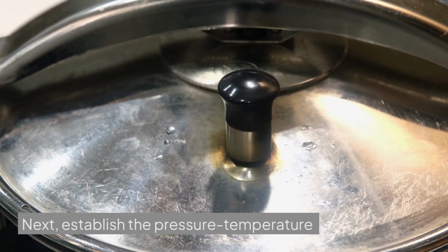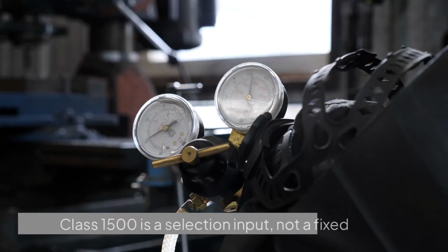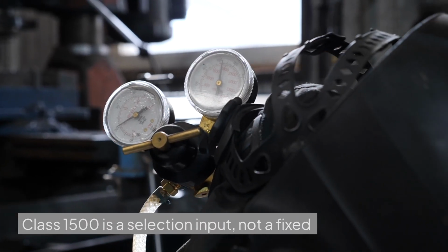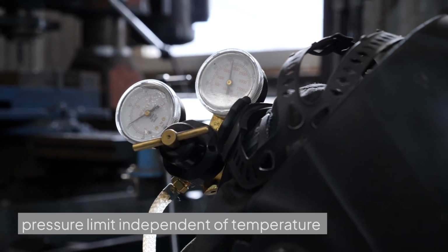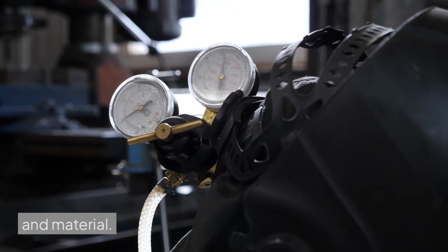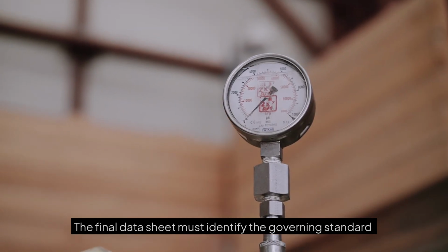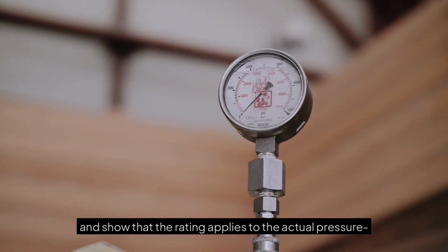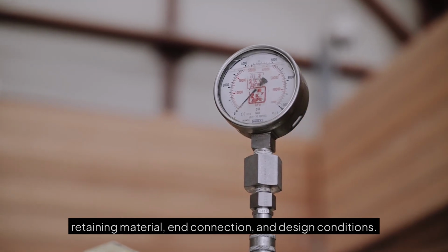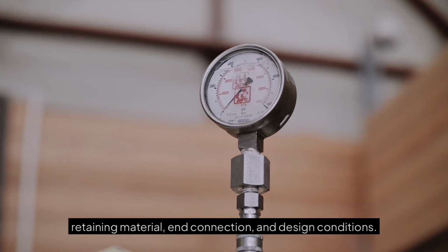Next, establish the pressure temperature basis. Class 1500 is a selection input, not a fixed pressure limit independent of temperature and material. The final datasheet must identify the governing standard and show that the rating applies to the actual pressure-retaining material, end connection, and design conditions.